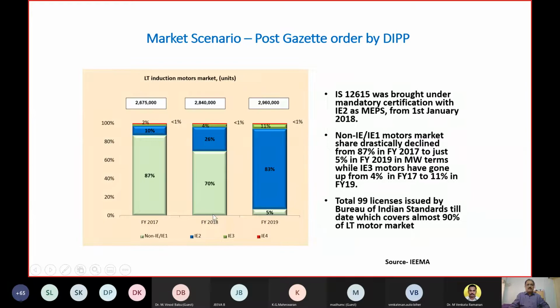In 2018, even after the GO from 1/1/2018, IEEMA reported, perhaps it must be up to March end, 70% of the population is non-IE motors. IE motors grew to around 30%. And in the year 2019, almost 95% of the motors manufactured are IE2, IE3 or IE4. Minuscule percentage of IE4 is also there. But still we have 5%, which is probably spillage. I am expecting that by 2020 or 21, this would have completely disappeared. And all the motors manufactured and sold in the market today in India through EMA members must be IE2 or IE3 or IE4. IE2 is compulsory, IE3 is voluntary, or IE4 is also voluntary.